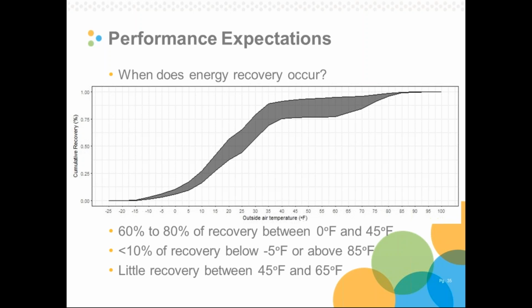So at the coldest temperatures, they've recovered 0 energy, and as we sweep through the entire year, they've all reached their full potential. Couple takeaways. 60 to 80% of energy recovery for these systems occurs between 0 and 45 degrees. So if we know that energy recovery systems are operating in cold to mildly cold temperatures, we're doing most of the recovery we're going to get in Minnesota. On the other side of that is less than 10% of recovery occurs below minus 5 Fahrenheit or above 85 Fahrenheit. We get these extremes in the state, but not frequently enough to really drive energy savings. And again, there's this midpoint between 45 and 65. We have mild energy savings here, either because the ERVs are off for economizer or because the loads are just quite small.